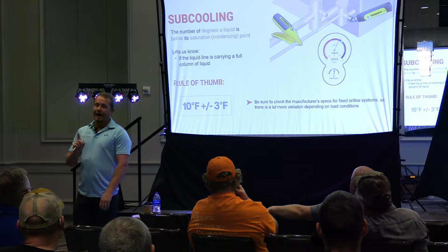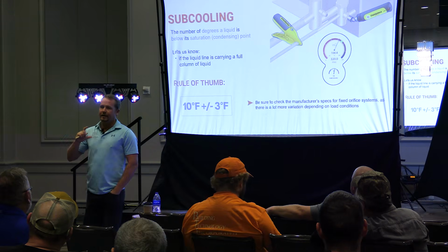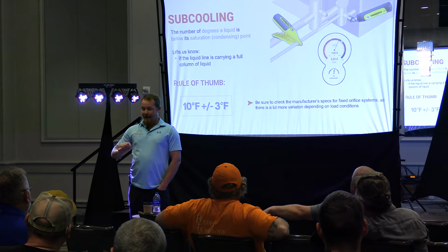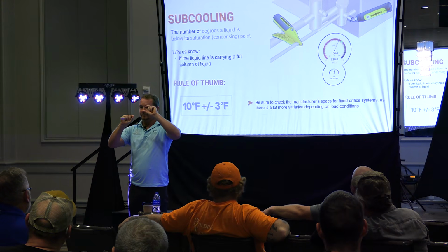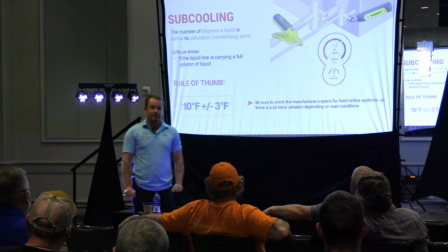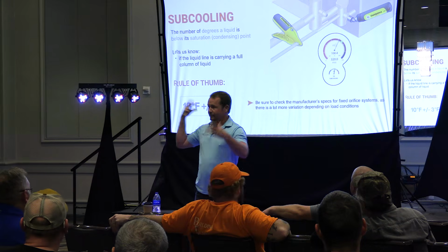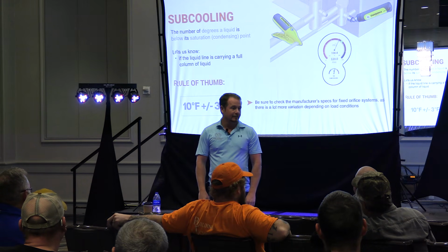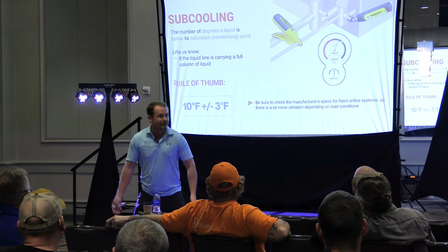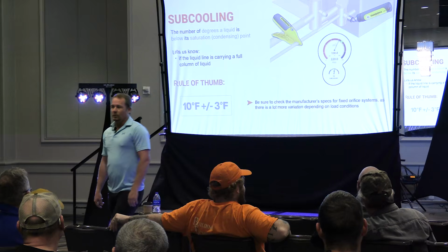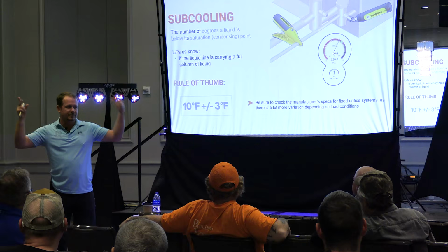So it's a trade-off. We actually don't want high subcool, because what are we doing to our effective condensing area in our condenser? Making it smaller. We're stacking liquid in that condenser. Now the area that actually does the condensing gets smaller and smaller, right? We're giving ourselves a smaller condenser the more subcool we get. Is this ringing a bell with anybody? Yeah, my guys, I put a piece of cardboard on the condenser. You're losing that. Right, that's what you're doing. You might as well be blocking the condenser off. You might as well be throwing some dirt on it. All right. So when people say, with every degree of subcool added, the efficiency increases by 1% or whatever, they'll say things like that.